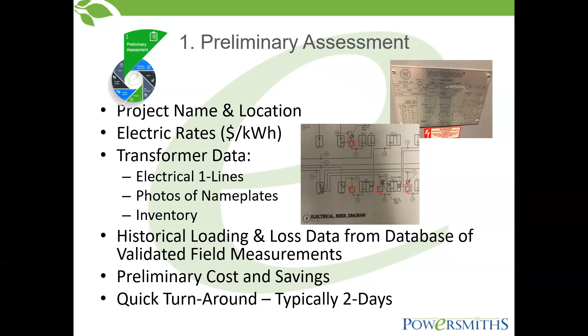Preliminary assessment: a lot of times the ESCO or the client will send us electrical one-lines, and we do some preliminary back-of-the-envelope calculations and say, this is what we think you're going to save in energy, because we've got a historical database that measures 500,000 transformers we've actually measured in the field. So we know a given transformer model is going to have this type of losses. We already know that, so we come out there and give that information.